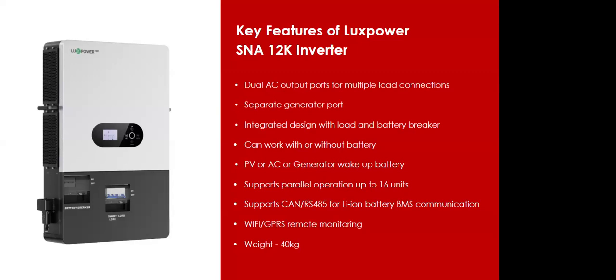This is a special function. We have issues with lithium batteries where, when they go too low, they shut down. That's how they're designed, as a protective function inside the lithium-ion batteries. But if an inverter doesn't have this feature, it cannot wake the battery up. You'd need to carry the battery to the supplier or get a battery booster to boost it before it wakes up again. This inverter comes with a feature that wakes up the battery by itself. Once there is grid or solar connected, it senses that a battery is connected but switched off, and it wakes it up and commences charging. It's a very interesting feature.